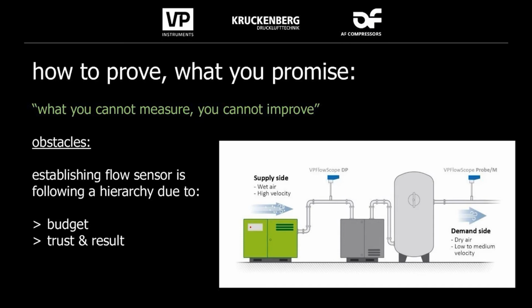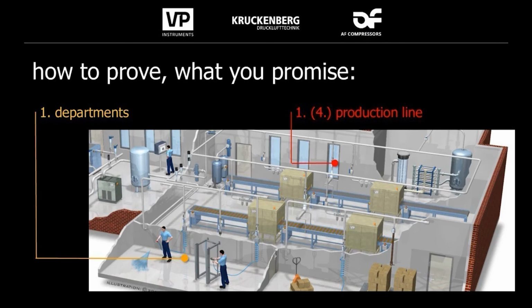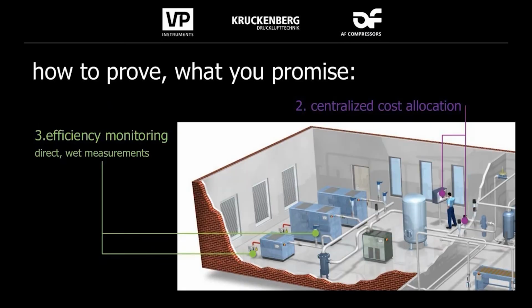So we were using differential pressure measurement probes to measure the efficiency of the old existing compressors, and also thermal mass measurement probes for production lines and individual departments, which is normally quite easy to establish a connection, or you can organize a shutdown, or you will find a date for a shutdown to implement your measurement devices. And in the end, we were facing the efficient monitoring of the centralized systems.